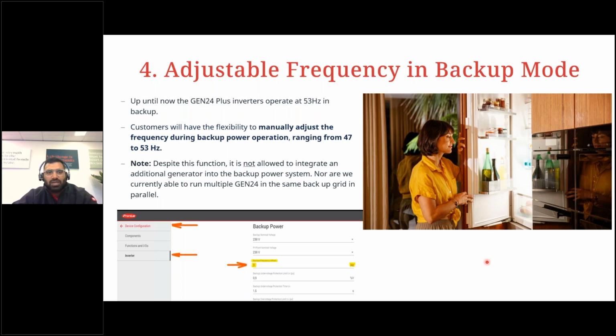Another cool feature that we have now is adjustable frequency in backup mode. Earlier, the inverter was always running at 53 Hertz in full backup. This was to kick out any other third-party inverters that are connected in the same backup circuit. But now it is possible to set the frequency anywhere from 47 to 53 Hertz in backup. So if the customer has some appliances, like a digital clock, that runs faster because the frequency is 53 Hertz, you can now offset it to somewhere between 47 and 53 Hertz in the device configuration. Under Inverter, you have backup frequency offset.